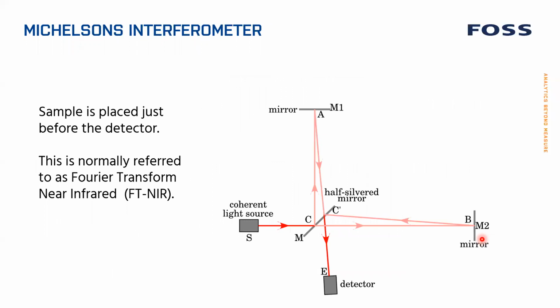The next one is what's called a Michelson interferometer. It's more common to call it an FT-NIR, where FT stands for Fourier transform, but the spectrometer itself is actually called a Michelson interferometer. This works in the way that you have a light source and a mirror that lets half of the light through. Half of the light goes here, is reflected on this fixed mirror, reflected back, and then to the sample, while the other half is reflected up here. This is a moving mirror, reflected back through the sample and to the detector. So the sample is normally positioned just before the detector.